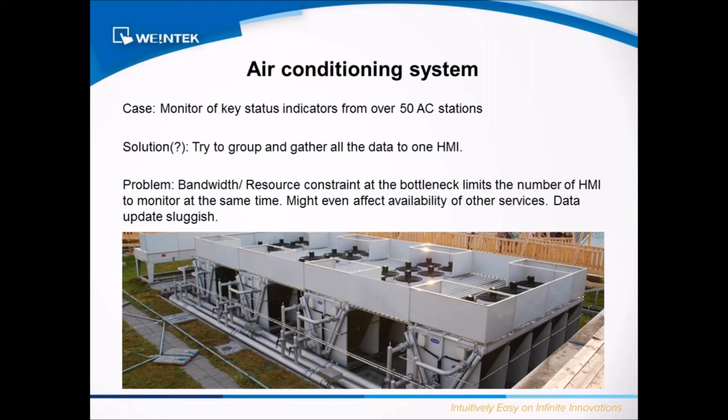and then we collect them eventually into one single unit. But the problem is that since you are collecting everything up to one unit, there's definitely going to be a bandwidth constraint or resource constraint on the HMI part. So there will be a bottleneck in your network that's going to limit the number of HMIs or the number of units that you can monitor at the same time. And this might even negatively affect your other services that are also using the network. So you have very sluggish data update rates, and your system just doesn't work if you have this kind of monitoring system.